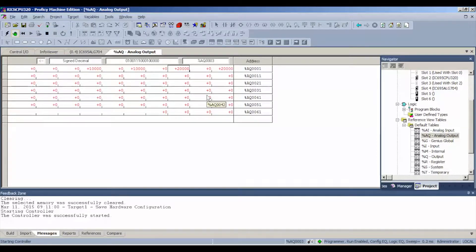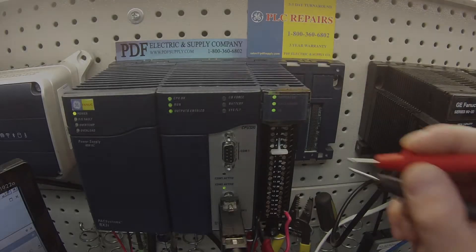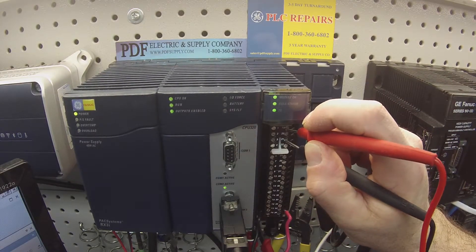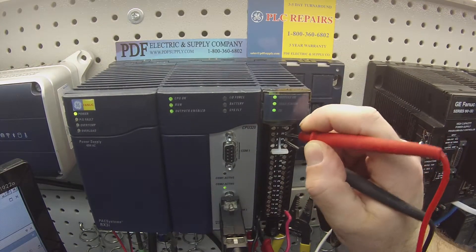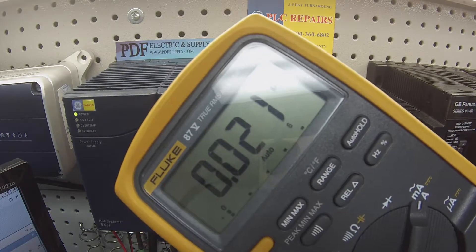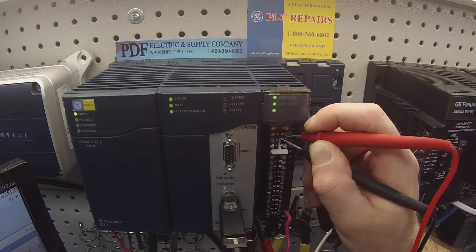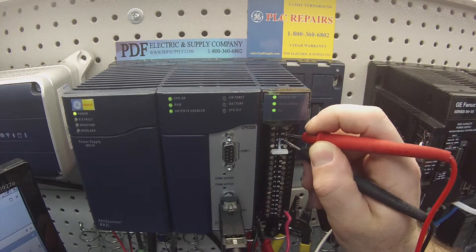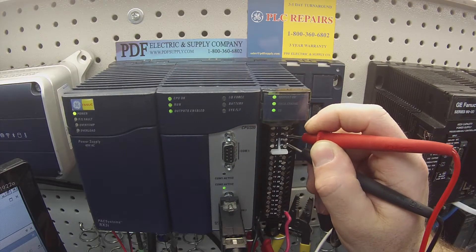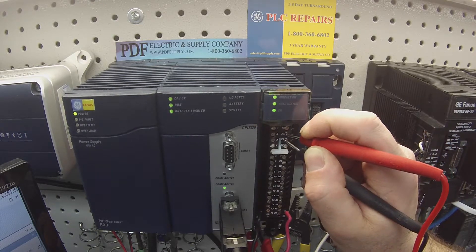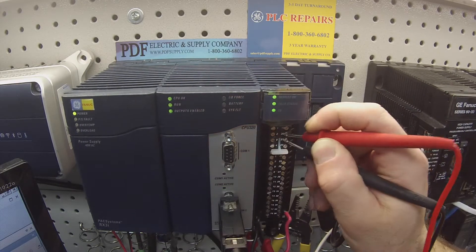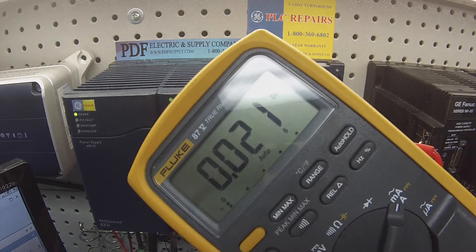So I'm going to attach my probes. I'm looking for a value of between 20 and 21 milliamps. I'm going to show you that. My negative lead is attached to terminal number 21, positive lead 20. Again it's the bottom nearest most screws on that channel, 21 milliamps. And 21 milliamps on our output number two.